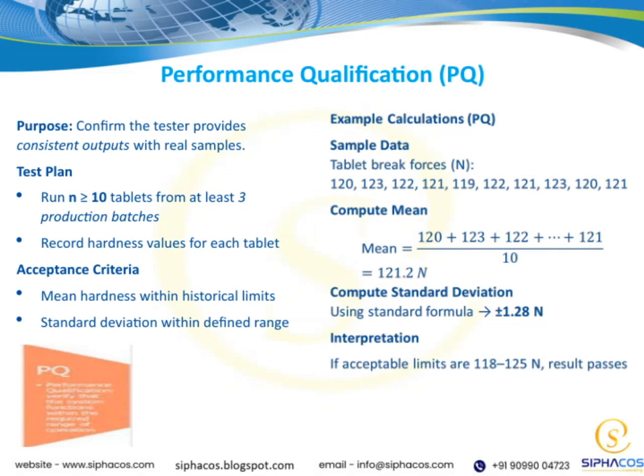The main purpose here is to confirm that the tester consistently produces reliable outputs when tested with real samples. This is crucial to ensure our process is dependable over time. For the test plan, we need to run at least 10 tablets from a minimum of 3 different production batches. This helps us verify that the testing process is robust across different batches and not just a one-time occurrence.